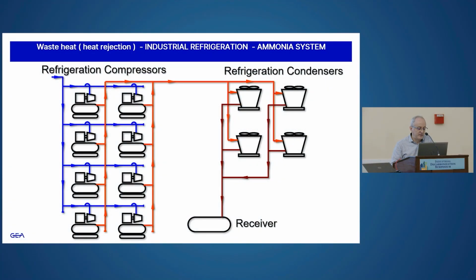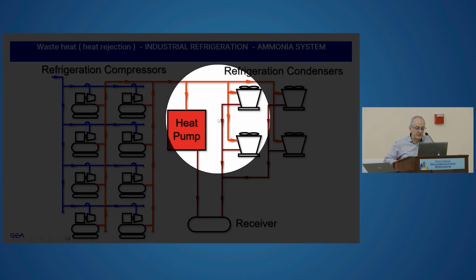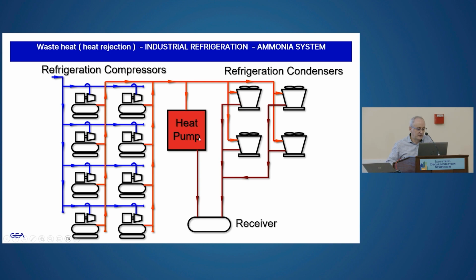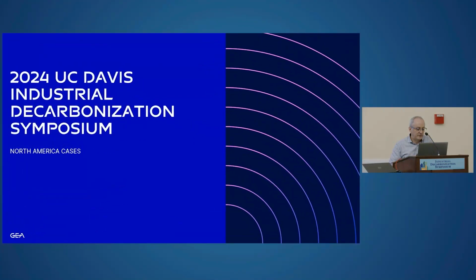A lot of these companies have refrigeration systems or chillers, and that's your heat source; the heat of rejection of those systems can go to the heat pump. So the opportunity is taking that heat of rejection, which today is being wasted on condensers or cooling towers, moving some part of that heat to the heat pump, mainly in food and beverage companies. We can see this, and we've done it.